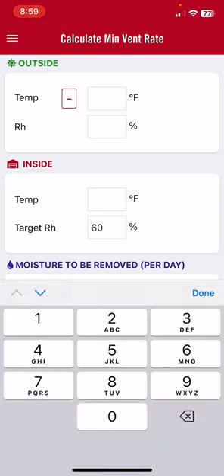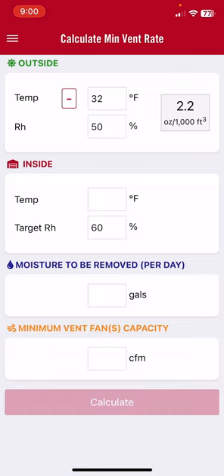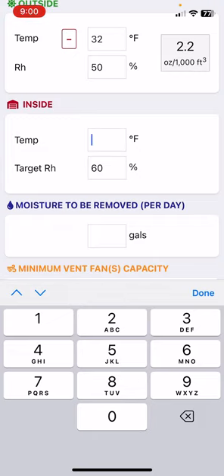First we put in our outside conditions. Let's say it's 32 degrees and the humidity is 50 percent. The app calculates the absolute humidity — how much moisture there is in every 1,000 cubic feet of air. In this case, at 32 degrees and 50 percent humidity, for every 1,000 cubic feet of air we bring in, we're going to bring in 2.2 ounces of water.